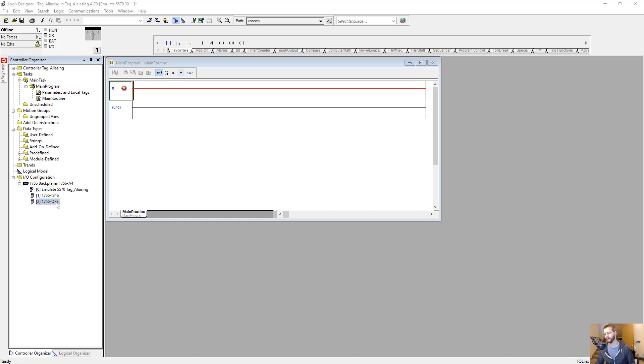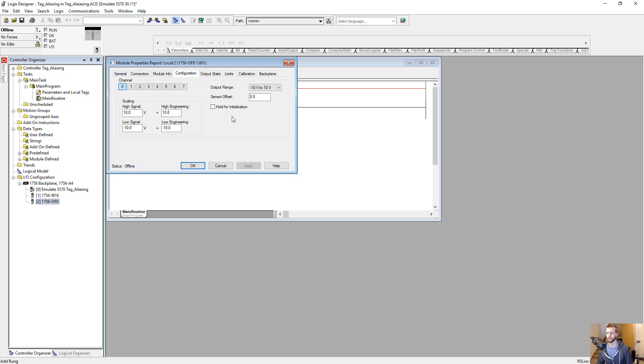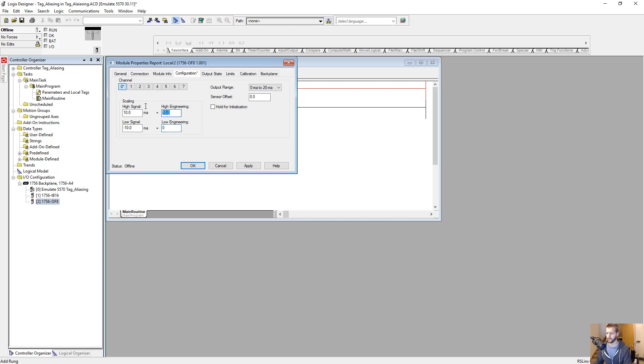Now I'm going to open up the OF8 properties again to set up the configuration. Our options are negative 10 to 10 volts, or 0 to 20 milliamps output signal. For the sake of simplicity, we're going to use a 0 to 20 milliamps signal. We're going to set up the scaling so that 0 to 100% in our tag corresponds to 0 to 20 milliamps. So if we write 100 to our output tag, it's going to put a 20 milliamps signal on the output module channel. Click OK.